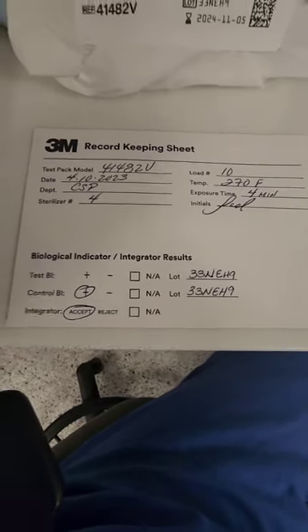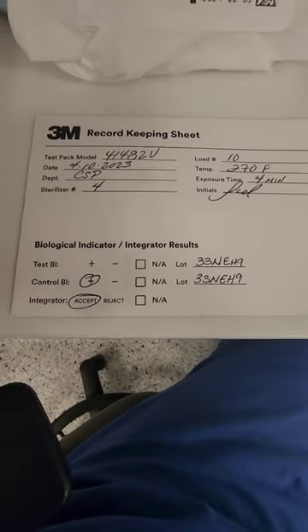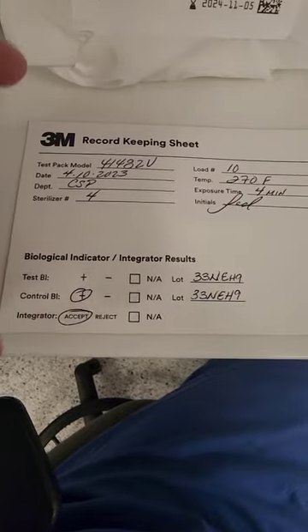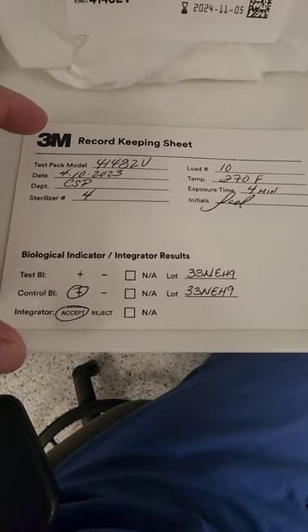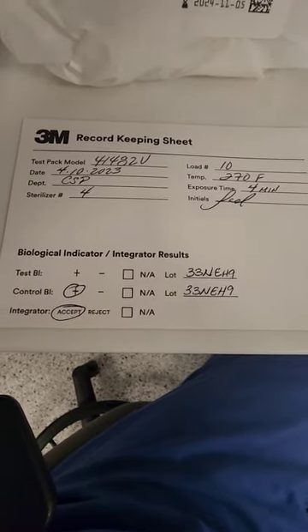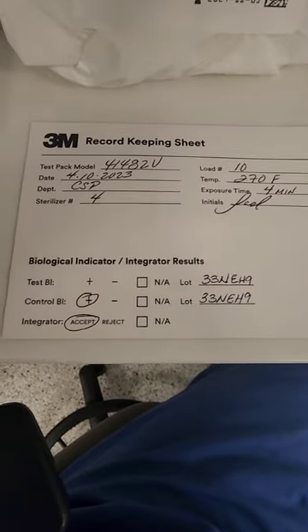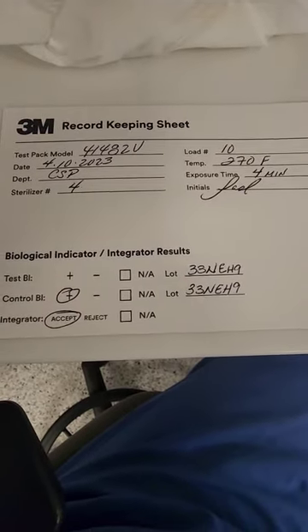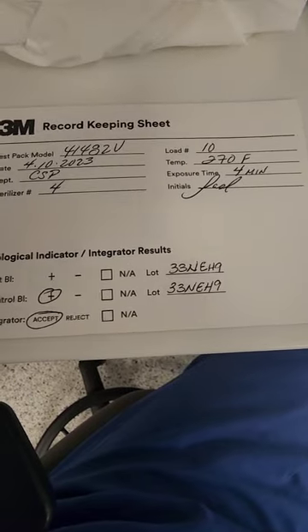So this is what it looks like when it's filled out all the way. All the information that's required on it, it should be legible, readable for anyone who pulls this record. This would be taped together with, or stapled together with the printout and the indicator and held for your records.